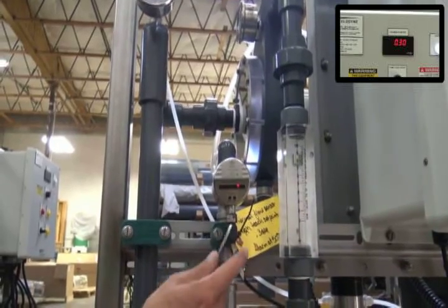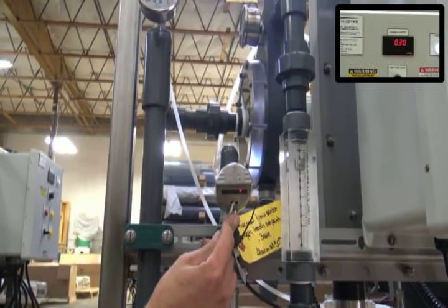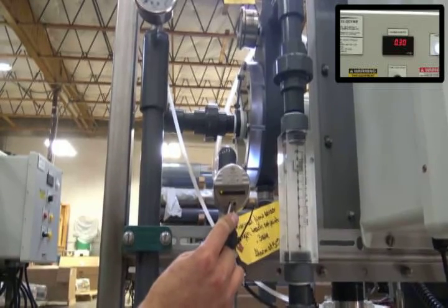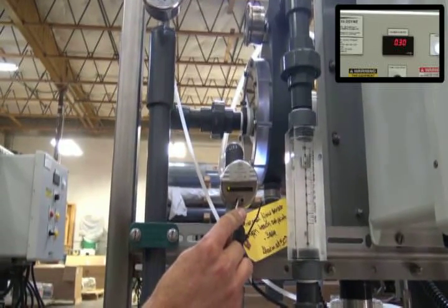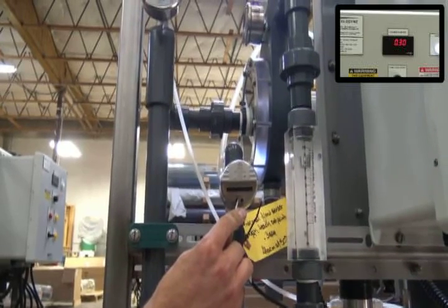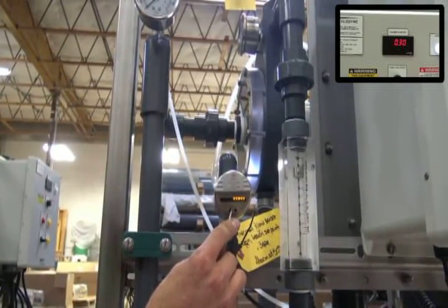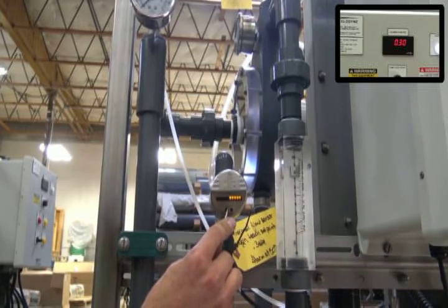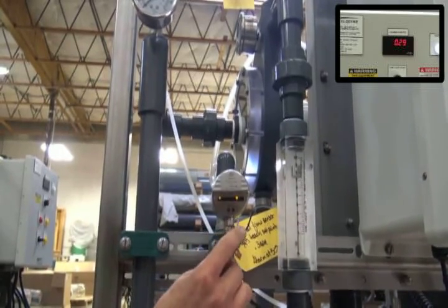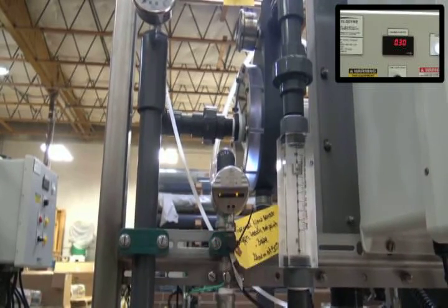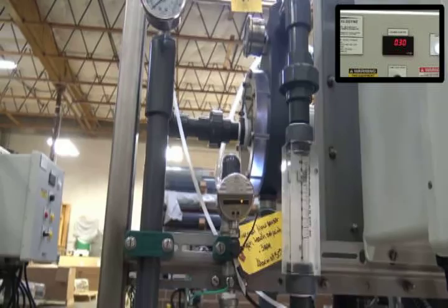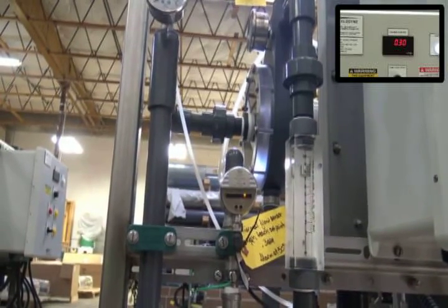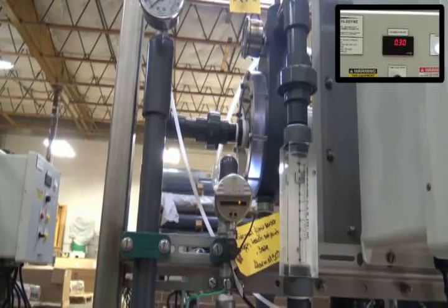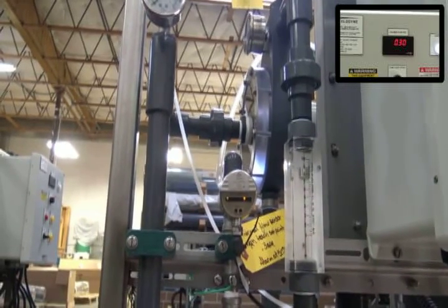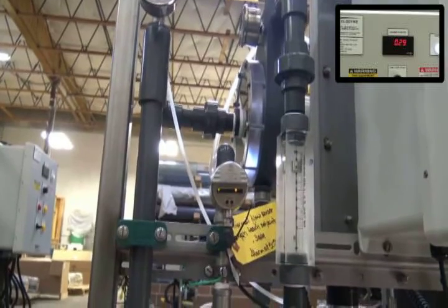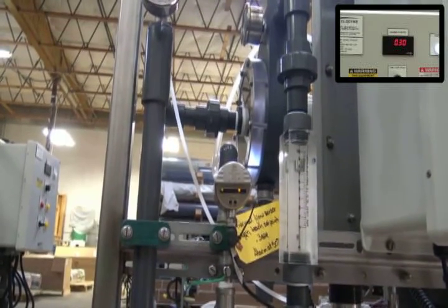To do that, we hold down the low teach, or the left button, for about 15 seconds. You see the green light go solid, it'll start blinking, and then keep holding it. Then you have the 4 orange lights, and then the other side will start flashing. Once it flashes, you let go. Now you see an orange light. That switched the states. Depending on the system and how that state needs to be, this is our normal operating area that we need to be in. So if it's not orange when it's not running or when it's in an alarm situation, then it's wrong, so you need to change that.